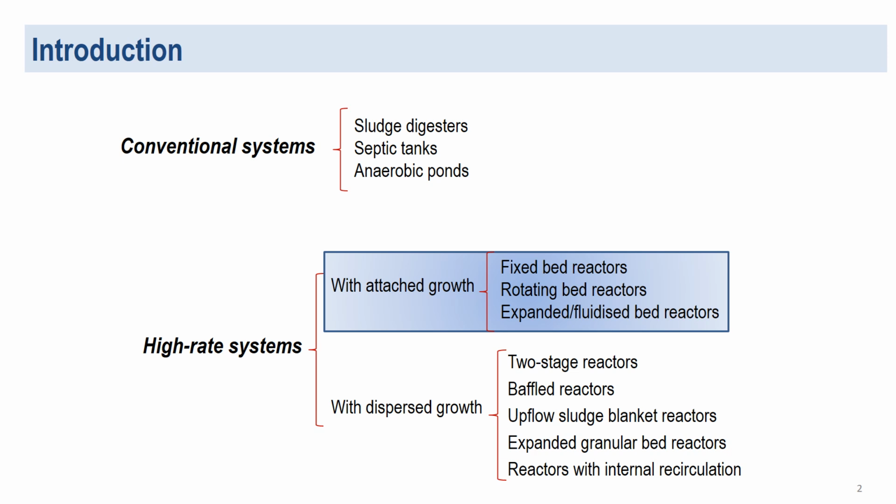With the advancement of research in anaerobic treatment, high-rate systems have been developed. These systems are primarily characterized by their ability to retain large quantities of highly active biomass, even under conditions of low hydraulic detention times. As a result, a high solids retention time is maintained despite the application of high hydraulic loads to the system. This leads to compact reactors with smaller volumes compared to conventional anaerobic digesters, while still achieving a high level of sludge stabilization.